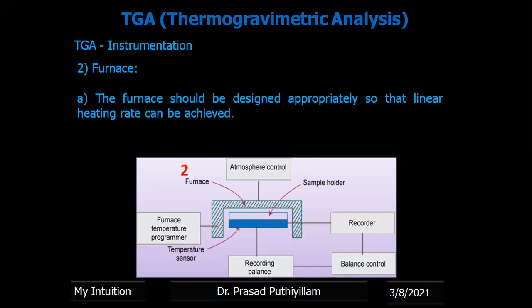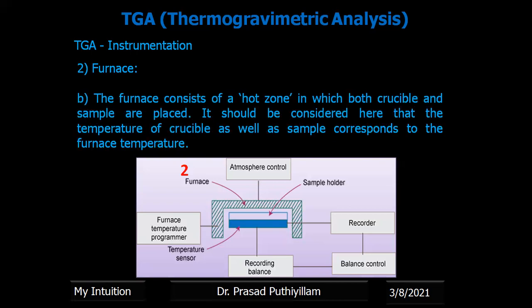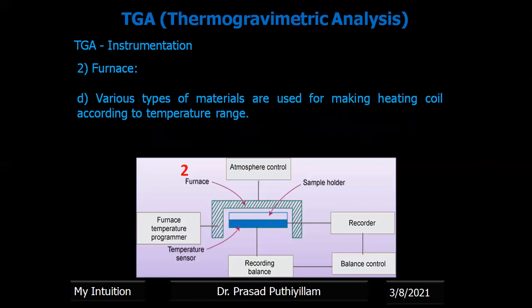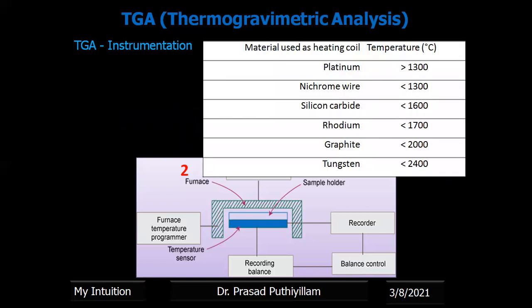The second component is the furnace. A furnace should be designed appropriately so that a linear heating rate can be achieved. The furnace creates a hot zone which includes the sample holder and the sample, and uniform temperature should be distributed to the sample. There are various types of heating coils used. Platinum can be used when the temperature requirement is above 1300 degrees Celsius. Then we can use nichrome wire, silicon carbide, rhodium, graphite, or tungsten.